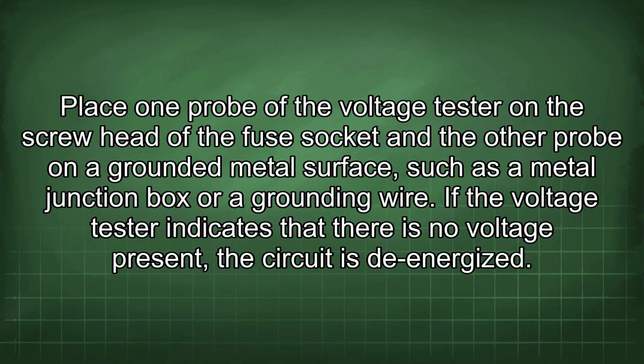Place one probe of the voltage tester on the screw head of the fuse socket and the other probe on a grounded metal surface such as a metal junction box or a grounding wire. If the voltage tester indicates that there is no voltage present, the circuit is de-energized.